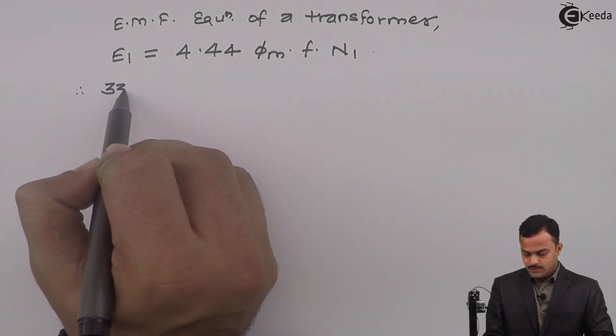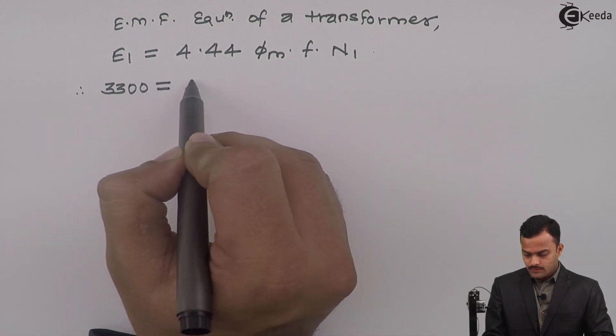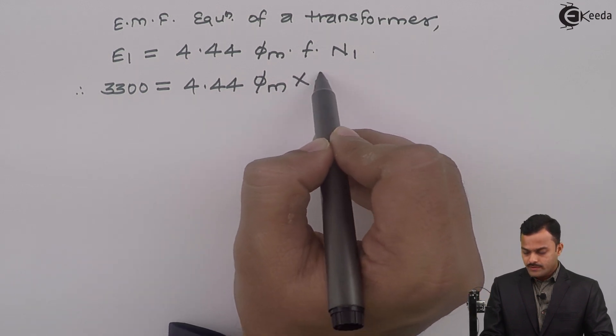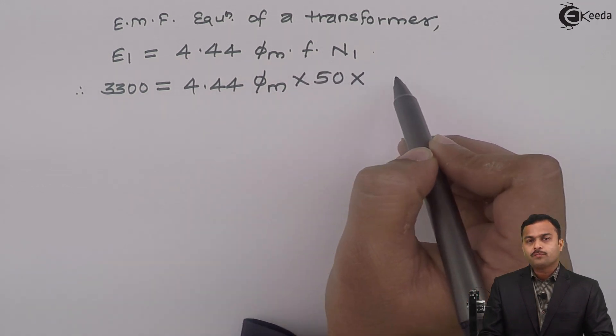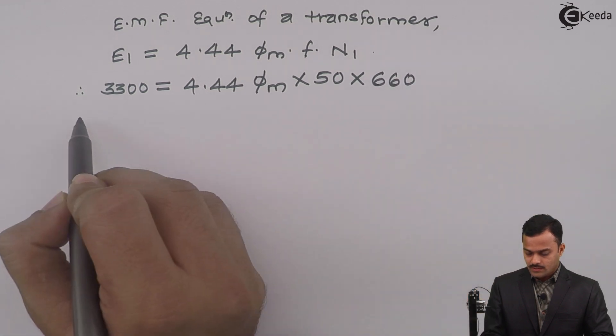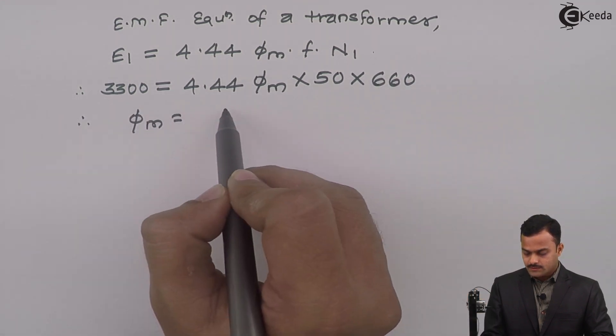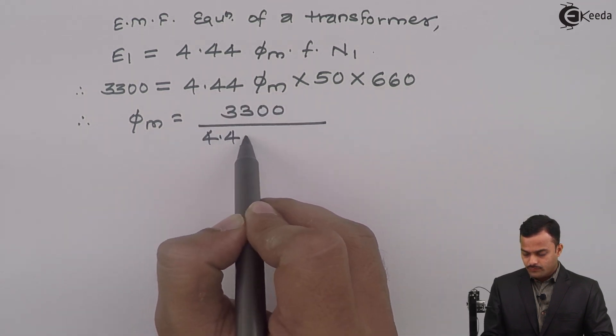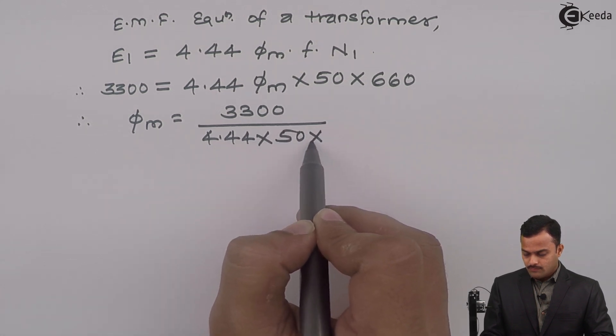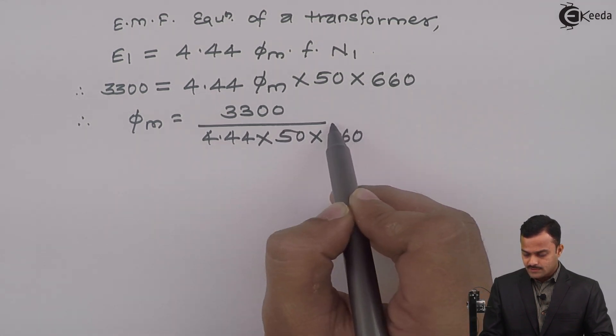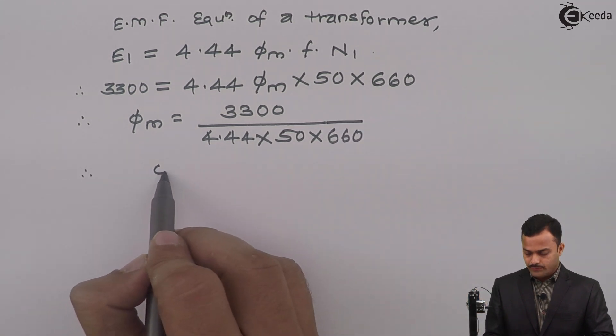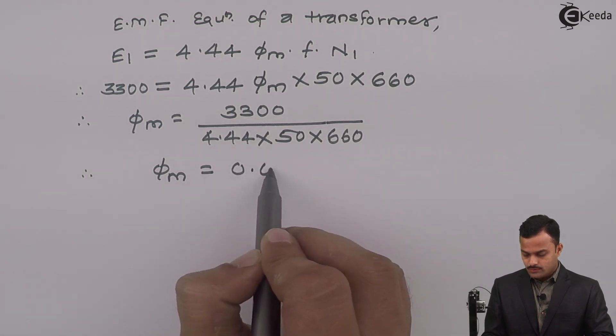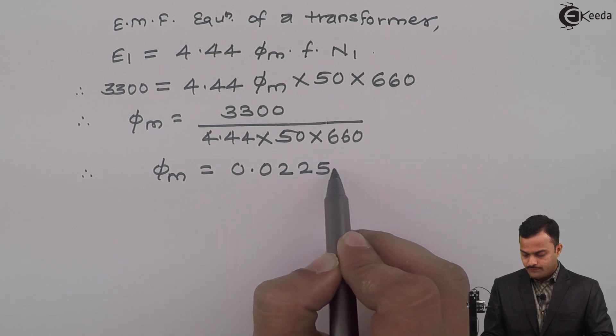So it says E1 equal to 4.44 phi M into F into N1. E1 is 3300 equal to 4.44, phi M is the maximum flux in the core that is unknown, frequency is 50, number of primary turns are 660. So phi M can be calculated 3300 divided by 4.44 multiplied by 50 multiplied by 660. So solution of this equation will give you maximum flux in the core phi M equal to 0.0225 Weber.